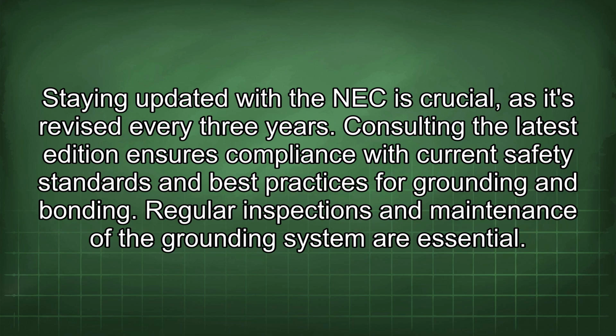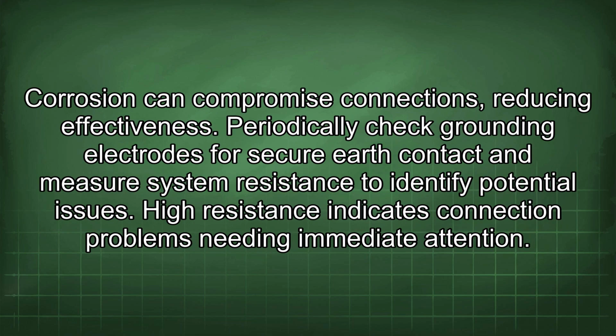Regular inspections and maintenance of the grounding system are essential. Corrosion can compromise connections, reducing effectiveness. Periodically check grounding electrodes for secure earth contact and measure system resistance to identify potential issues. High resistance indicates connection problems needing immediate attention.